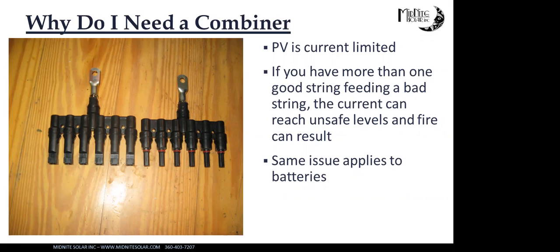But the one thing that I see gets missed a lot is batteries. I don't know how many systems I've seen with multiple strings of batteries and no overcurrent protection. And the same really holds true there. If you've got 8 strings of batteries and one string has a problem, the other 7 strings are going to gang up on that string and you're going to have a big old meltdown. But if each string had a properly sized overcurrent protection, when that one string had a problem and the other ones tried to gang up on it, that overcurrent protection would open and the problem would go away. So that's just something to keep in mind.